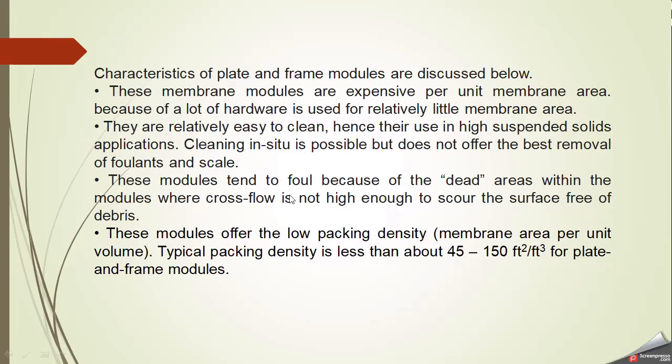These modules tend to foul because of the dead areas within the modules where cross flow is not high enough to clean the surface of debris. These modules offer low packing density, typically around 45 to 150 square feet per cubic foot of volume. So these are seldom used and not popular nowadays.